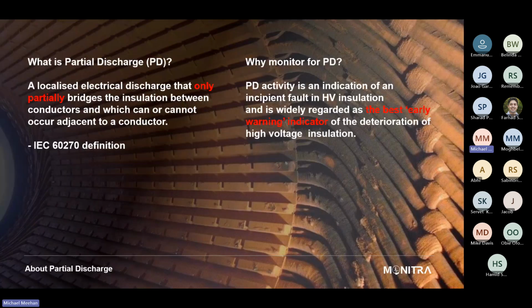So when we think of PD, obviously that's one of the key failure modes that we're looking at. In terms of what is the definition, it's always best to go off what the standards say, and obviously IEC have provided a nice definition for us, IEC 60270. So PD is a localized electrical discharge that only partially bridges the insulation between conductors, which can or cannot occur adjacent to a conductor. So it's important to reference partially bridged, because when we're testing, typically we're testing a healthy asset. And what we're seeing if we see PD is potentially that health degrading.